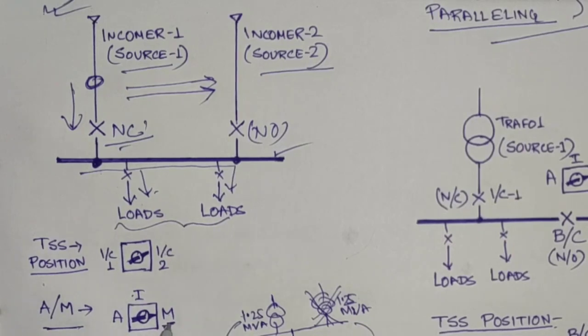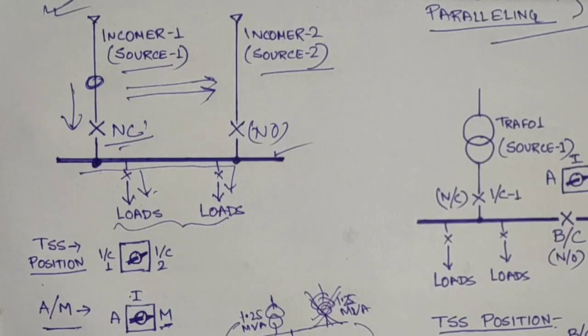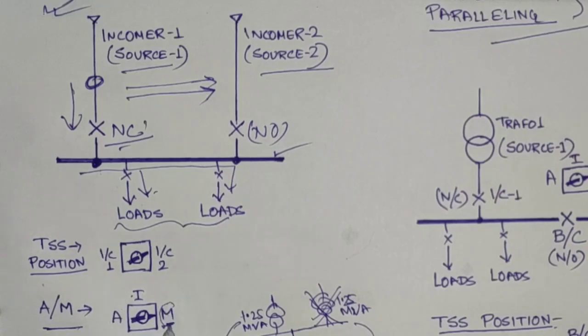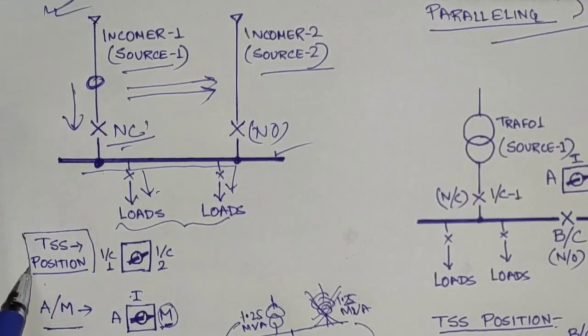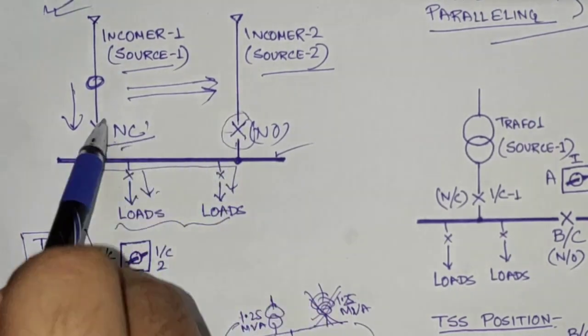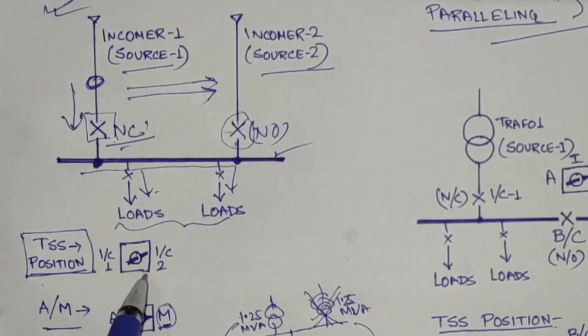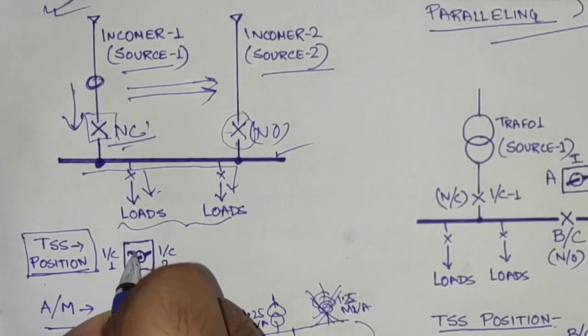The auto-manual switch shall be at manual position, allowing the operator to manually switch a breaker on or off. There is another selector switch called the Trip Selector Switch (TSS). When Incomer 2 is closed, the two sources will come in parallel momentarily, so one breaker must be tripped. Since Incomer 1 is currently closed and we want to shift load to Incomer 2, the trip selector switch will be set to the Incomer 1 position — because Incomer 1 is the one to be tripped.